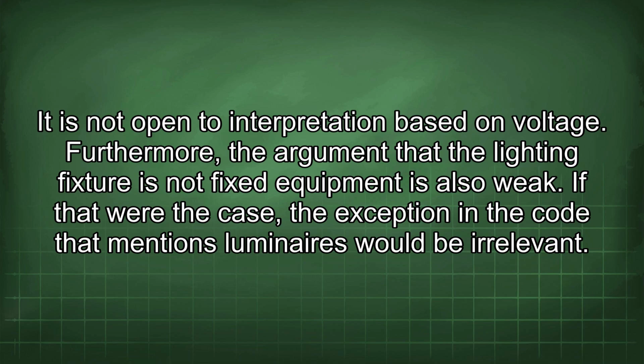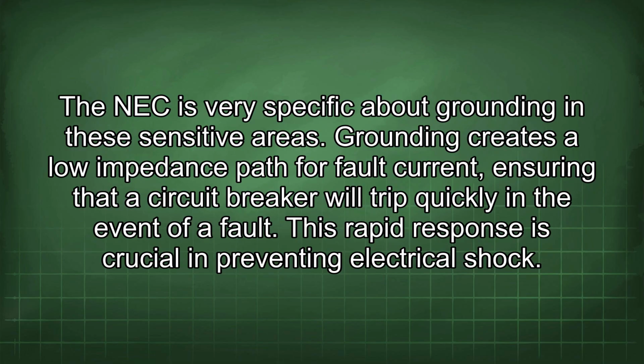Furthermore, the argument that the lighting fixture is not fixed equipment is also weak. If that were the case, the exception in the code that mentions luminaires would be irrelevant. The NEC is very specific about grounding in these sensitive areas. Grounding creates a low impedance path for fault current, ensuring that a circuit breaker will trip quickly in the event of a fault. This rapid response is crucial in preventing electrical shock.